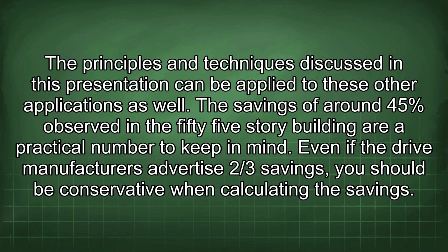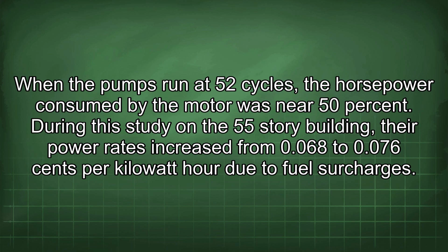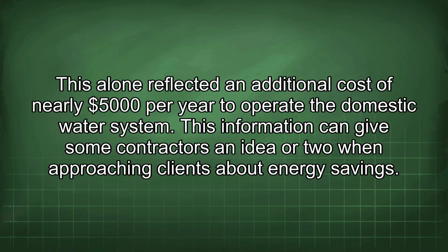The savings of around 45% observed in the 55-story building are a practical number to keep in mind. Even if the drive manufacturers advertise 2/3 savings, you should be conservative when calculating the savings. When the pumps run at 52 cycles, the horsepower consumed by the motor was near 50%. During this study on the 55-story building, their power rates increased from 0.068 to 0.076 cents per kilowatt-hour due to fuel surcharges. This alone reflected an additional cost of nearly $5,000 per year to operate the domestic water system. This information can give some contractors an idea or two when approaching clients about energy savings.